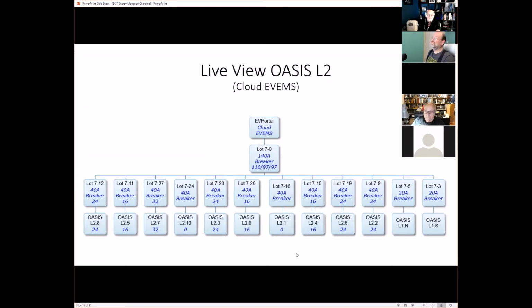And so here is a view of the Oasis system running as a cloud EVMS. We were able to see how much power it allocated to each EVSE. On the Lot 7.0 breaker, it's reporting that it was using 110 of the 112 amps available on line A, or line 1, 97 on line 2, and 97 on line 3, which means there was room for some EVSE to use more. But at this time, there were a couple of EVSEs that nobody was using, and the chargers that were in use were not on B, C phases, so we couldn't turn anybody up to take advantage of those. Most of the people that could use the power were using line 1 at some point, and there were only 2 amps available on line 1.